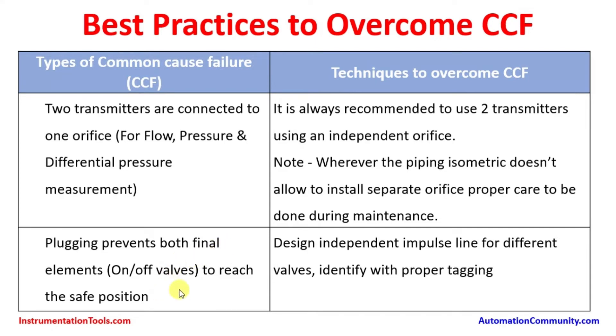Plugging prevents both final elements from reaching a safe position. Design independent impulse lines for different valves and identify them with proper tagging. From the instrument air header, the main instrument air going to the valve shall use independent tubing for operation.